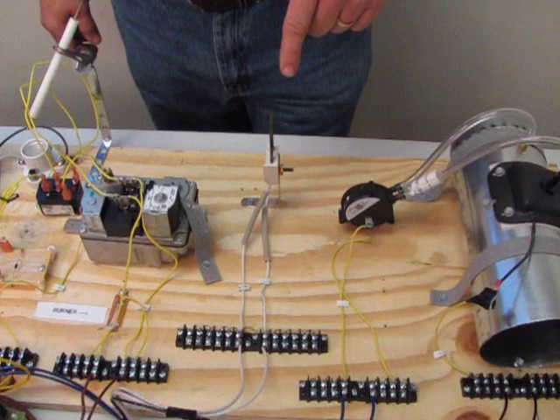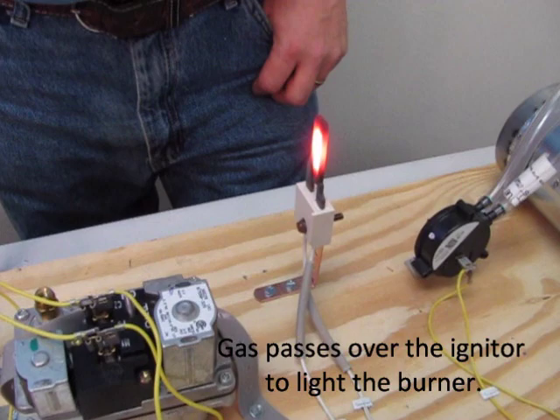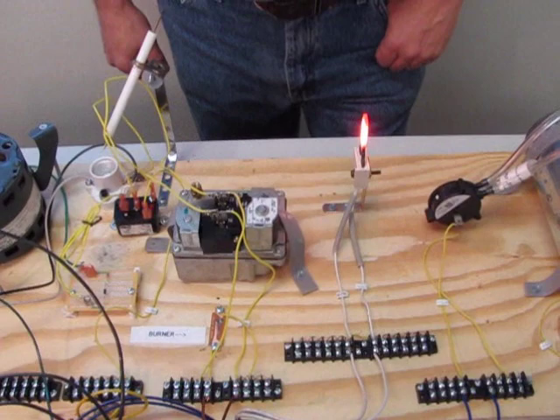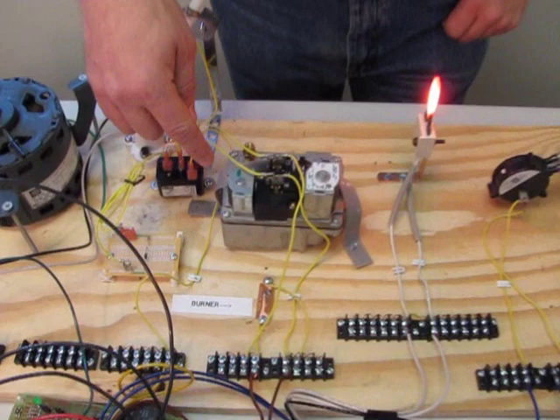And when the board reads all this, it's going to turn on the igniter to light the gas. This particular one is a glow-type igniter. It gets really hot. And then in a few seconds, you'll hear the gas valve click.